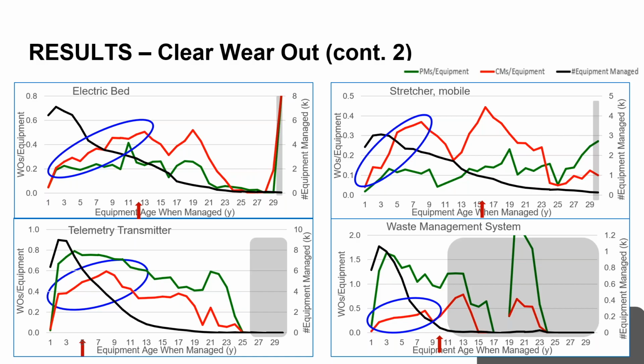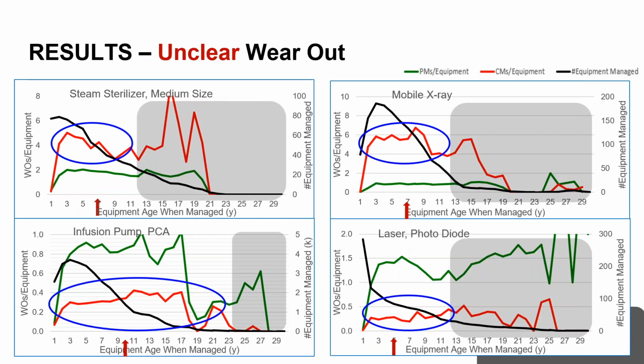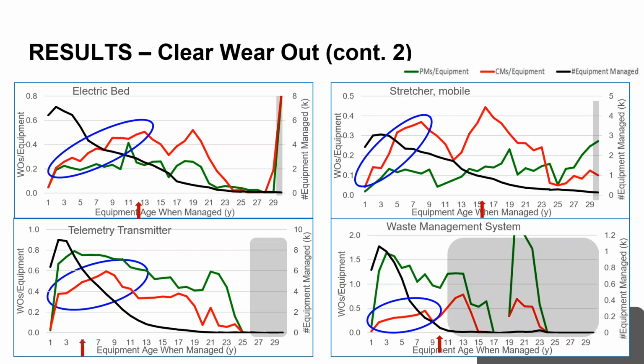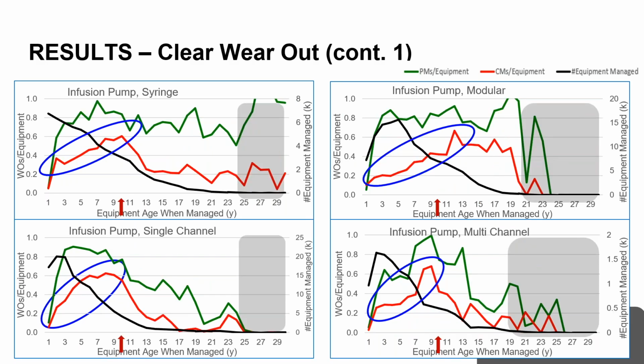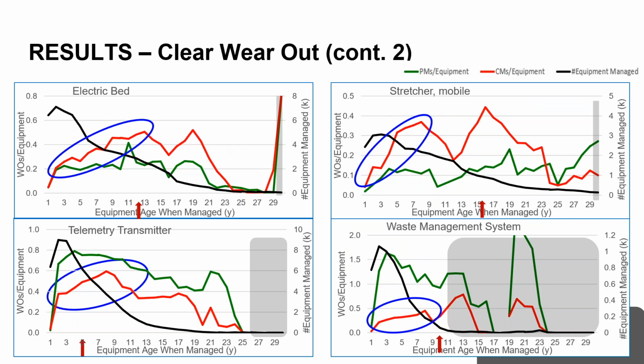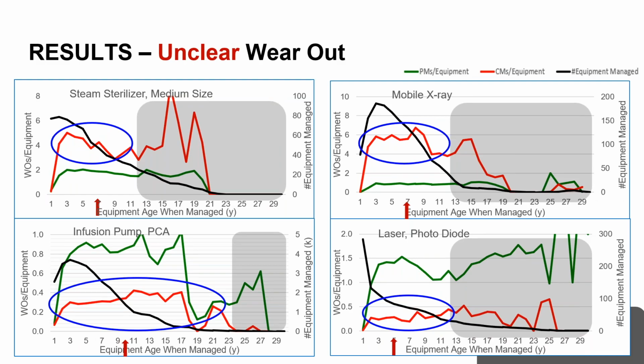And by the way, the PMs are actually fairly flat in most cases. Sometimes you see a little bit of rise of PMs because, remember, we go back 20 some years, 30 years here. Previously, Joint Commission was not demanding 100% PM completion rate. So actually you will see that some of the PMs actually got increased for more recent ages, not because they needed, but because we were mandated to do it, okay? And when we have larger numbers, these gray zones then become smaller, but when we have small numbers, the gray zones are bigger.